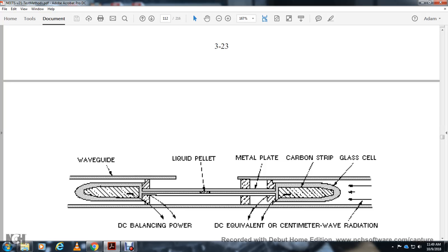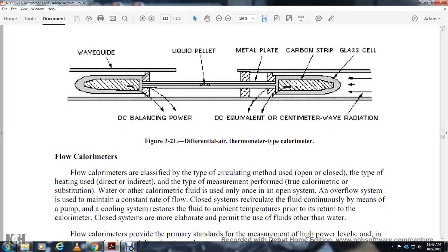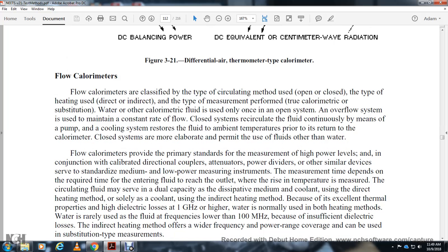Waveguide, liquid pellet, DC balancing power, metal plate with a carbon strip, glass cell, the DC equivalent. Centimeter wave radiation flow calorimeter. Flow calorimeters are classified by the type of the circulating method, open or closed, the type of the heating, direct or indirect, and the type of the measurement performed, true calorimeter or substitution. Water or other calorimetric fluid is usually used, only once for the open system.